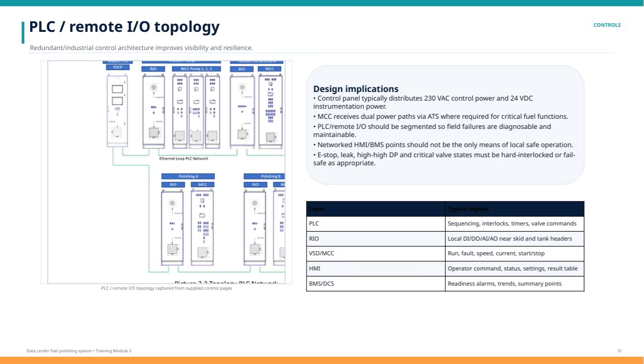The table summarizes the typical signals handled at each control layer. PLCs manage sequencing, interlocks, timers, and valve commands. Remote I/O units handle local digital and analog inputs and outputs close to the skids and tank headers. Variable speed drives and motor control centers monitor run status, faults, speed, current, and start/stop commands. HMIs provide operator control commands, status updates, and settings feedback, while building management systems or distributed control systems track readiness alarms, trends, and summary points. This structured approach ensures a robust and maintainable control system, which is vital for complex operations like data center fuel polishing systems.